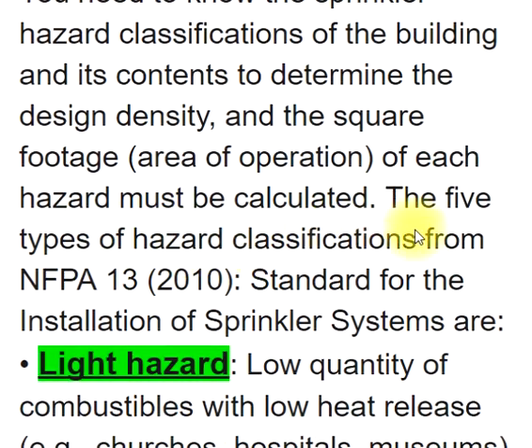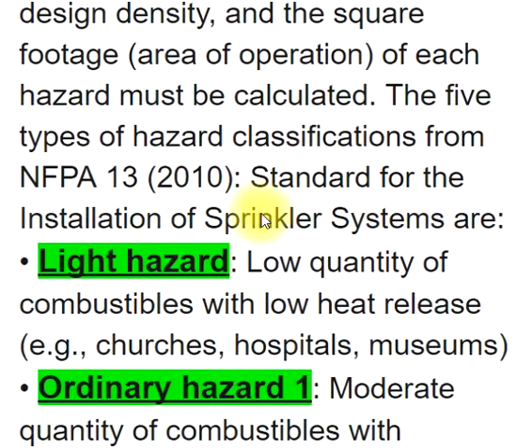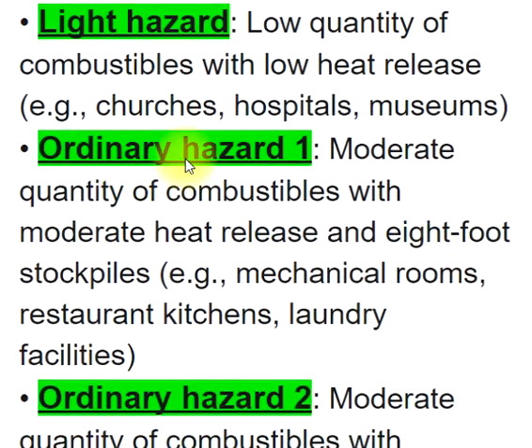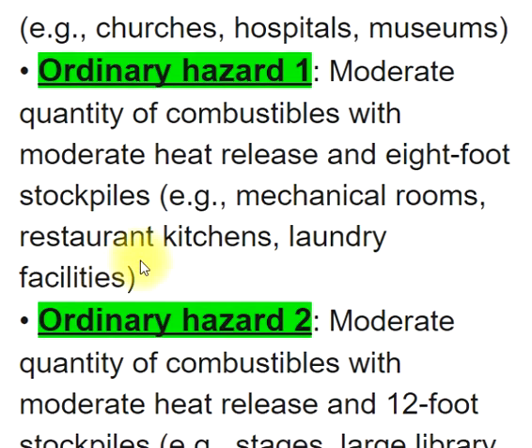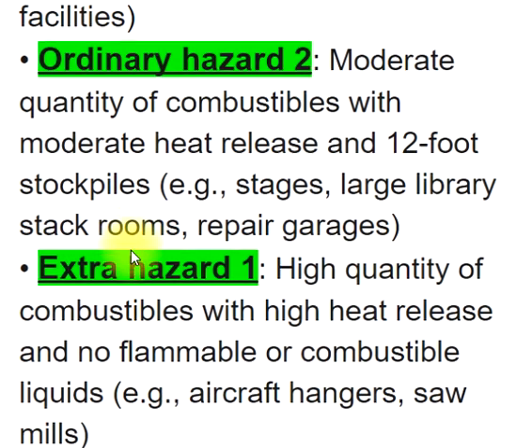The five types of hazard classifications from NFPA 13 (2010 standard for the installation of sprinkler systems) are: Light Hazard — low quantity of combustibles with low heat release, e.g., churches, hospitals, museums. Ordinary Hazard 1 — moderate quantity of combustibles with moderate heat release and 8-foot stockpiles, e.g., mechanical rooms, restaurant kitchens, laundry facilities. Ordinary Hazard 2 — moderate quantity of combustibles with moderate heat release and 12-foot stockpiles, e.g., stages, large library stack rooms, repair garages.